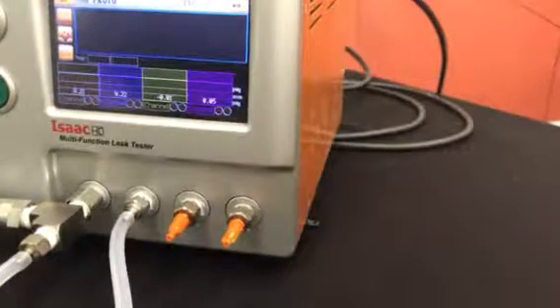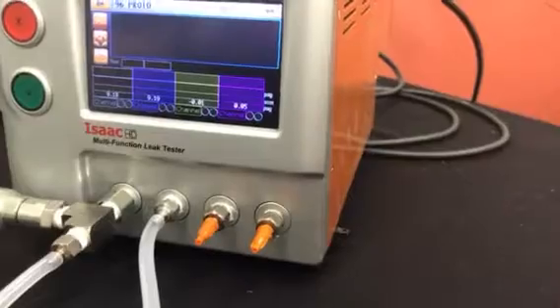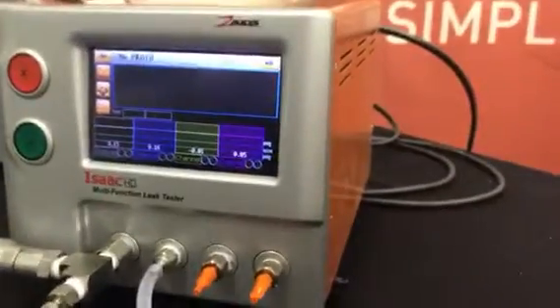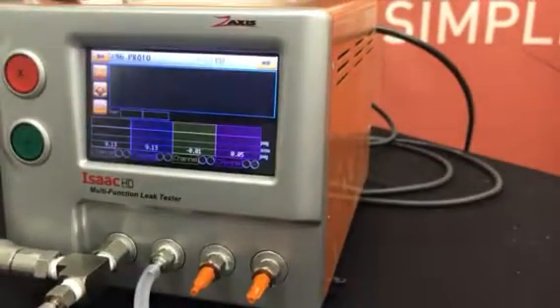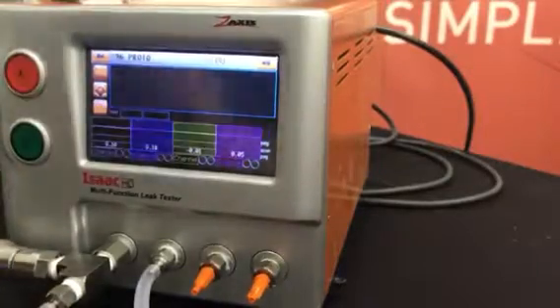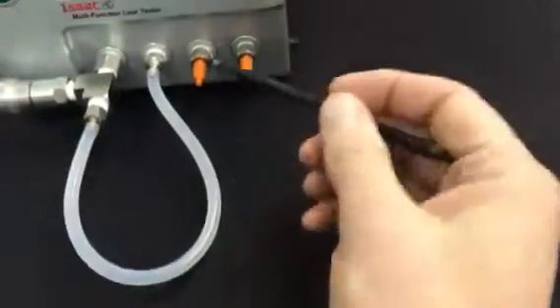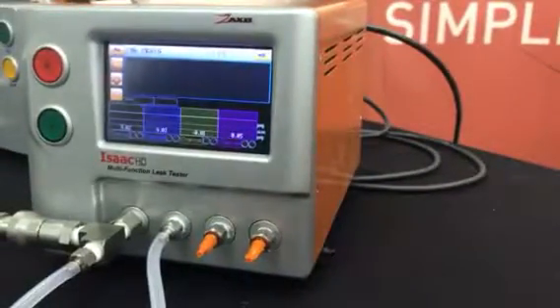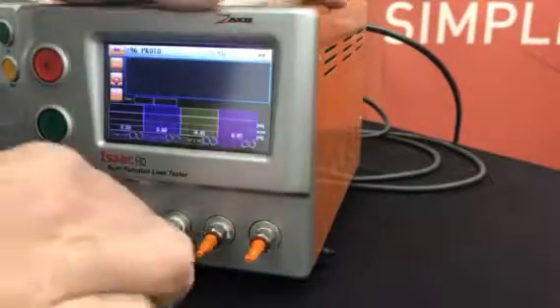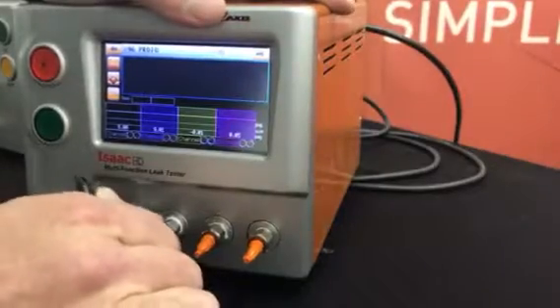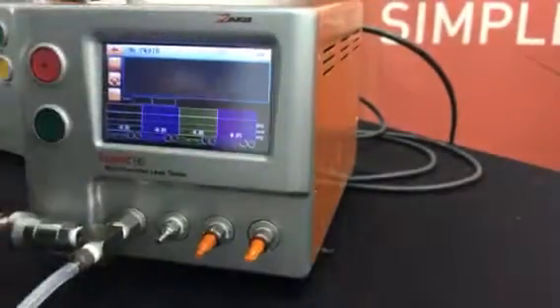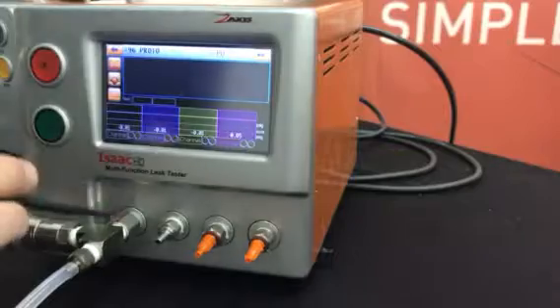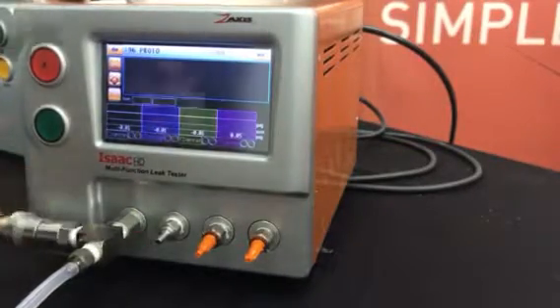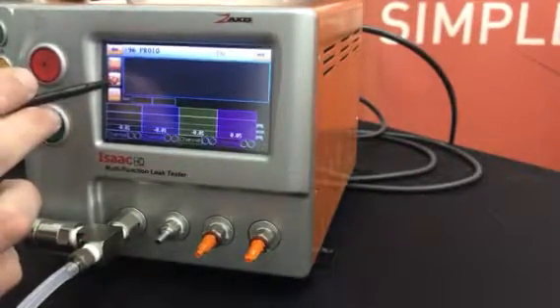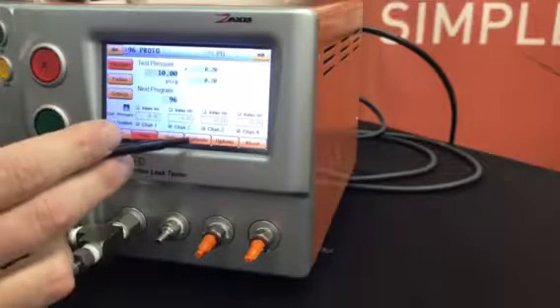All right, I'm gonna walk you through this quick, simple procedure so you guys can get that new sensor calibrated. As you can see here, I tied channel 1 to channel 2, but when you put your sensor in, the first thing you want to do is do a tare. So unhook the tube, so both channels. Channel 1 is the one you're replacing, so make sure that's open to atmosphere.